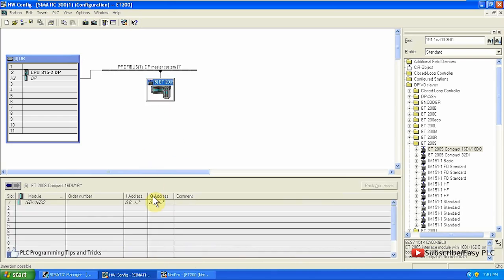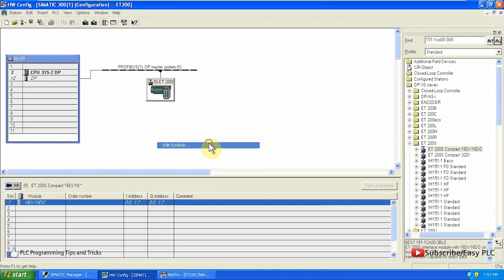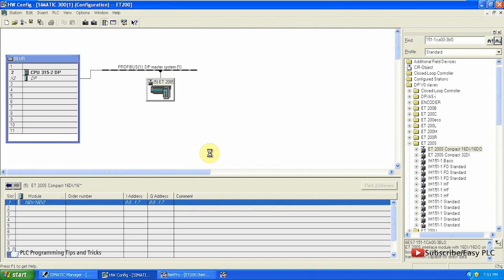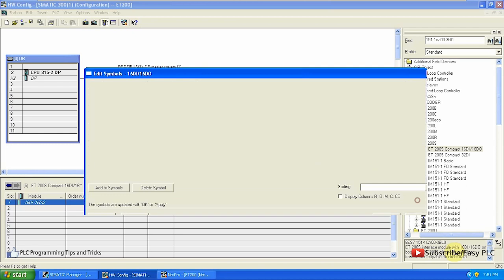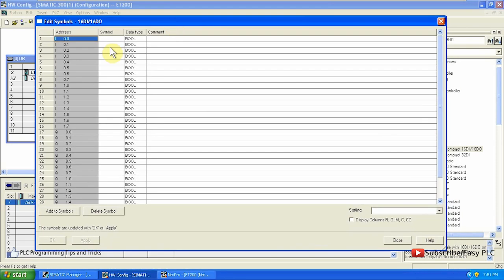Coming back to hardware configuration, we can see the I address and Q address — the inputs and outputs addresses. In the edit menu, you can see this module has 16 inputs starting from I0.0 up to I1.7, and 16 outputs starting from Q0.0 up to Q1.7. We can also add some symbols to these addresses in this menu.